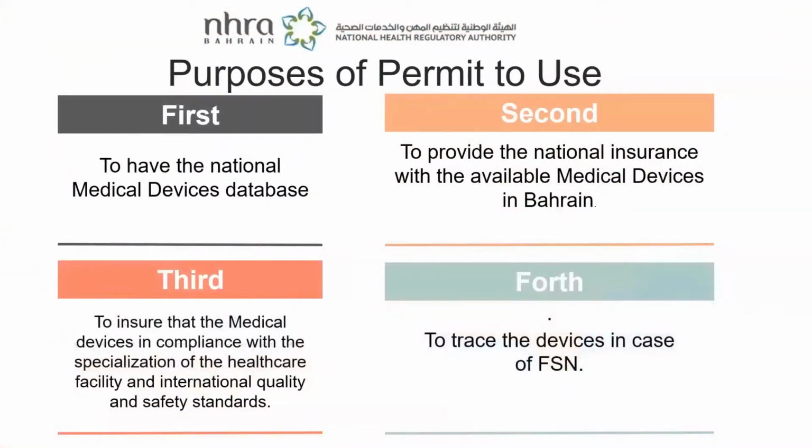Okay, what are the purposes of permit use? We have 4 purposes. First of all, to have a national database for medical devices. Second, to provide the national insurance with the available medical devices in Bahrain. And third, to ensure that the medical devices are in compliance with the specialization of the healthcare facilities and international quality and safety standards. Fourth and last, to trace the devices in case of field safety notices, to make sure that all the devices are safe to use.